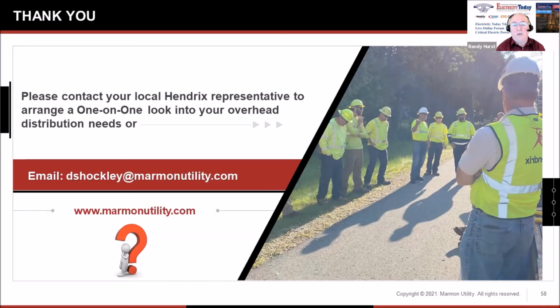Do you allow for extra radial ice to be resilient to extreme weather due to climate change? Well, we're able to model as much ice as you want on that conductor in PLS-CADD, and that will get back to how sturdy a pole you need. If you're anticipating more ice in the future, I know that the National Electric Safety Code is changing their wind and ice loadings due to climate change. I know CSA is looking to change their wind and ice loading as well. But if I tell PLS-CADD I have a half inch of ice, or 4 inches of ice, the same calculations are done. It's just going to change the type of pole that I need. Do we have that capability? Absolutely, positively. Great, and that all improves the reliability of our system.